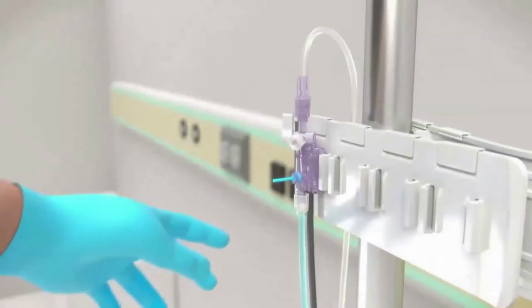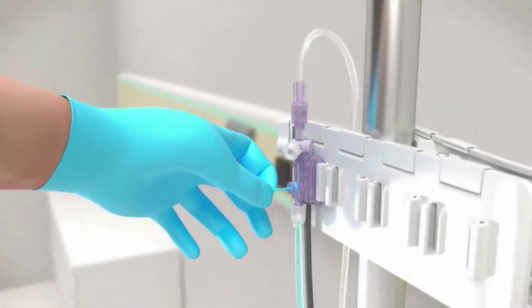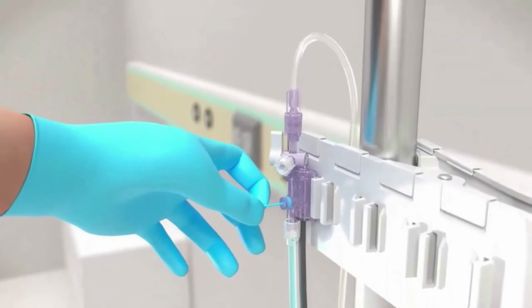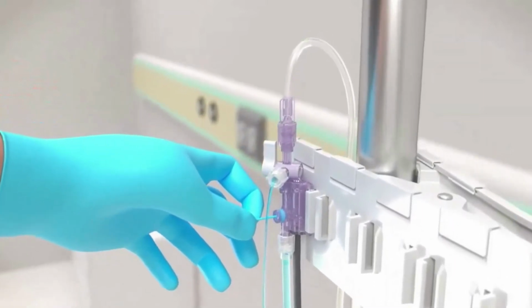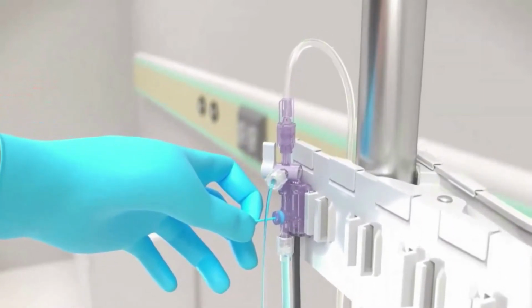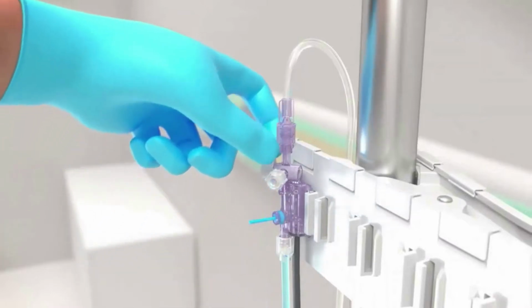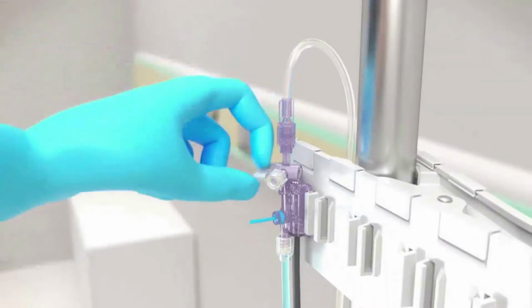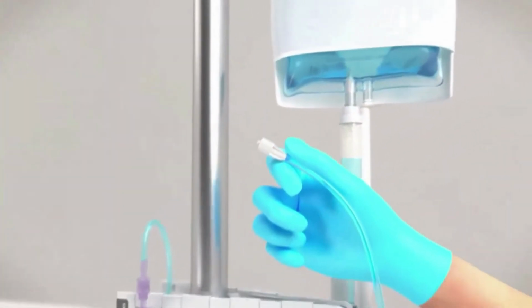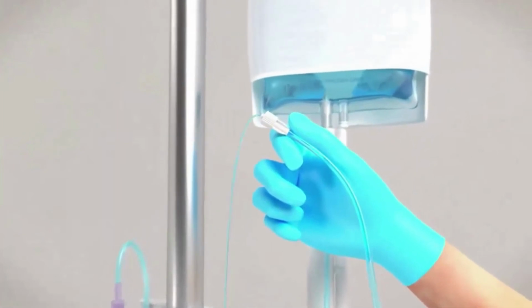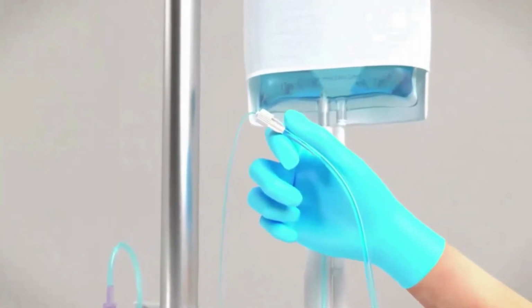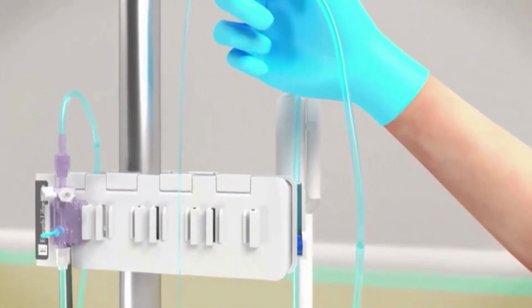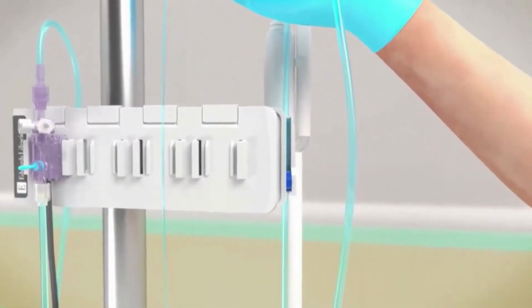Pull the snap tab flush device to deliver the flush solution through the TruWave transducer and out through the vent port's vented cap. Remove all air bubbles. Close the vent port by turning the stopcock toward the cap. Holding the pressure tubing in an upright 45-degree angle, pull the snap tab to flush the remaining part of the line through the end of the tubing. Visually inspect the line to ensure that all air bubbles are removed.